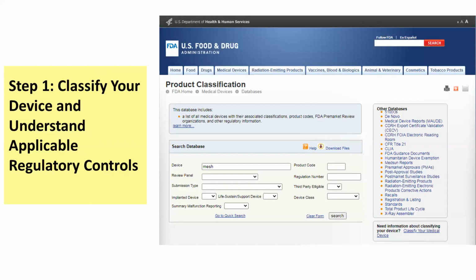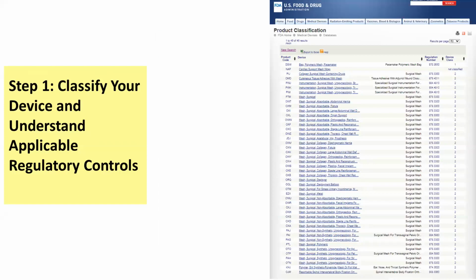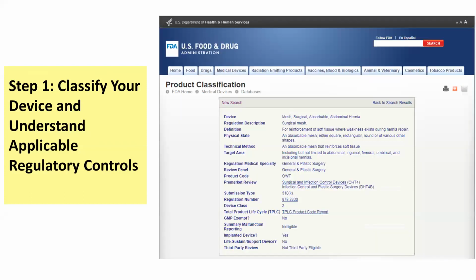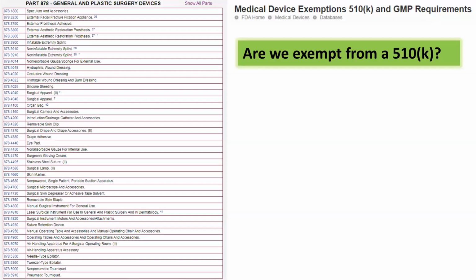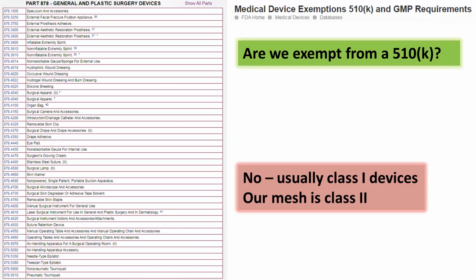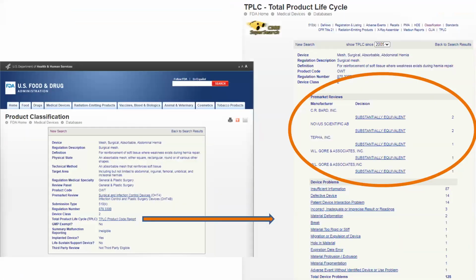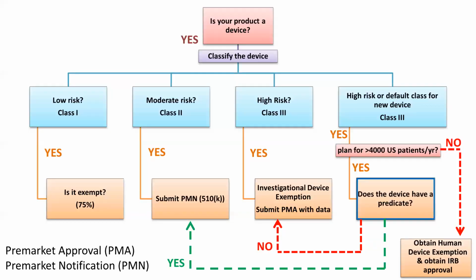So if we look up hernia mesh in the product classification database, we get 46 different sections. But if we look at absorbable mesh, that will take us here, where we can see that we are in device class 2. That's great. We can do a 510K if we can prove equivalence. And we're not exempt from a 510K because we're class 2, not class 1. But if we click through, we can find the names of the other devices we can try to show our predicates. So you can use the database to try to link yourself to target your substantial equivalence.